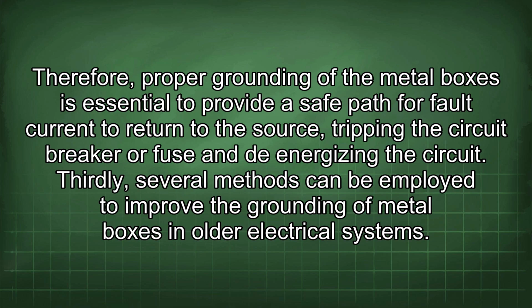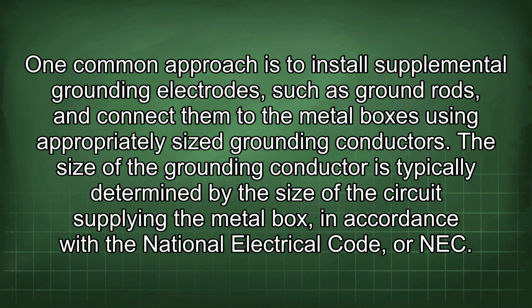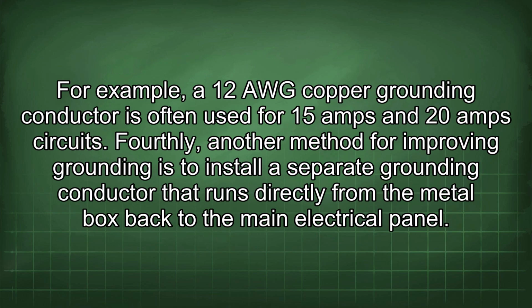Thirdly, several methods can be employed to improve the grounding of metal boxes in older electrical systems. One common approach is to install supplemental grounding electrodes such as ground rods and connect them to the metal boxes using appropriately sized grounding conductors. The size of the grounding conductor is typically determined by the size of the circuit supplying the metal box in accordance with the National Electrical Code, or NEC. For example, a 12 AWG copper grounding conductor is often used for 15 amp and 20 amp circuits.